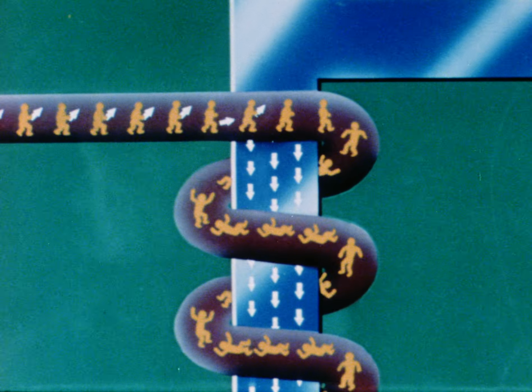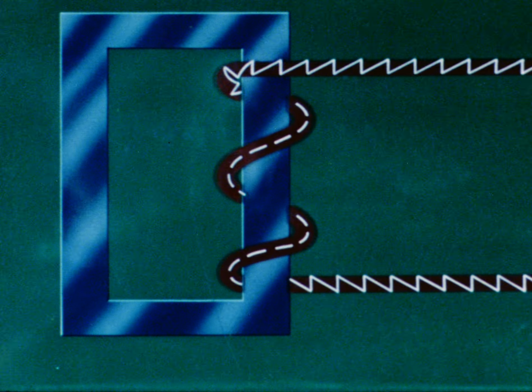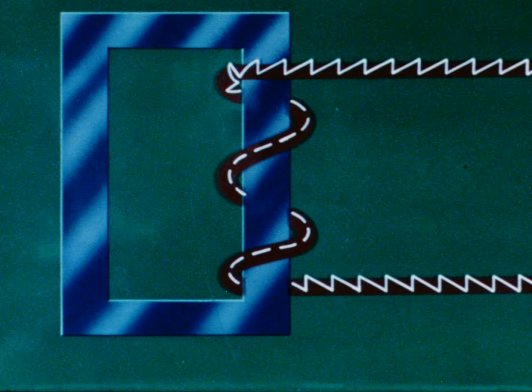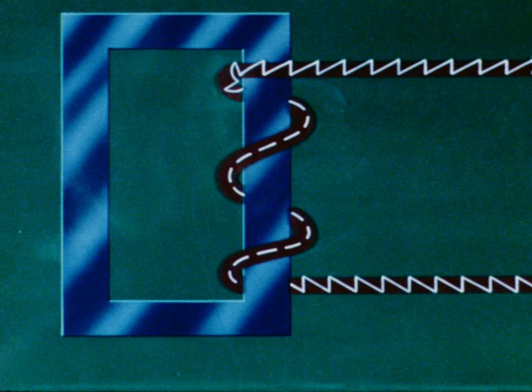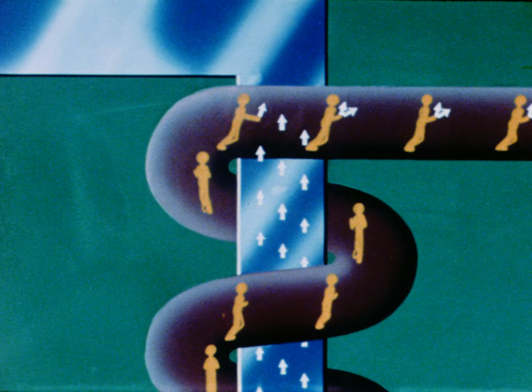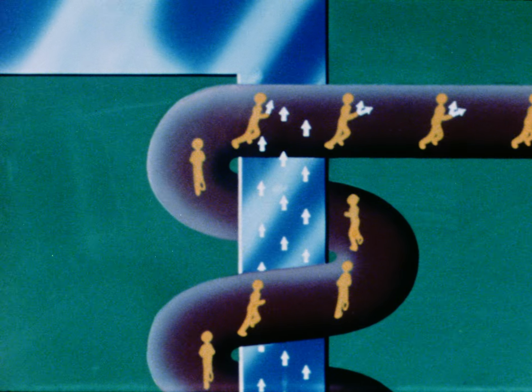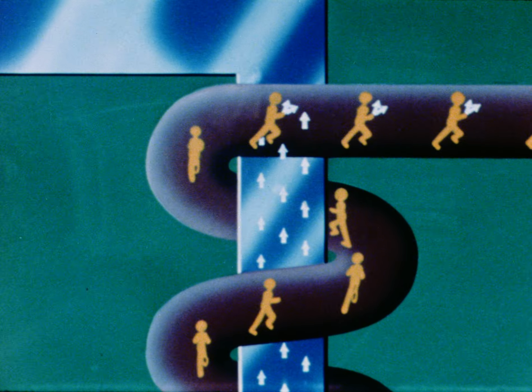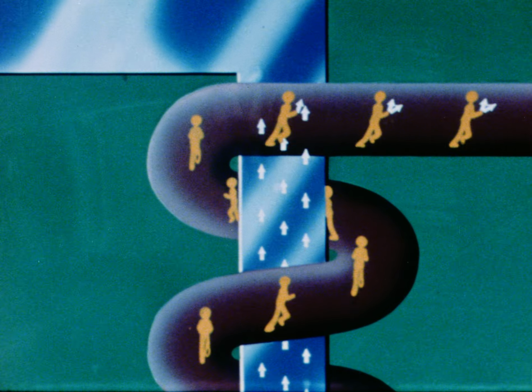Let us imagine a number of little men representing the high voltage. As they race around the steel core, they create a magnetic field. We might say that each of them throws an arrow into the core as he goes by. Now, if another wire, a bigger one this time, is wound around the other side of the core, something else happens. The magnetic flux induces current into the low voltage windings. In other words, other little men pick up the arrows. But things are different now. The little men are bigger and there are not as many. And each one picks up not one, but several of the arrows.